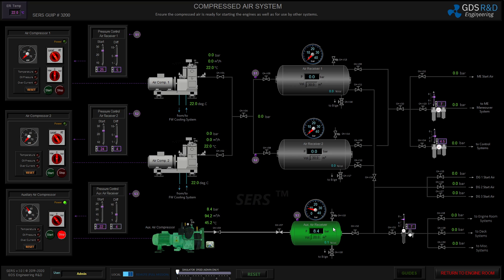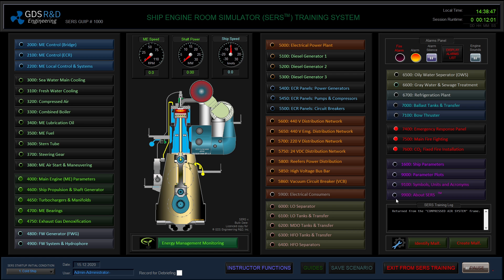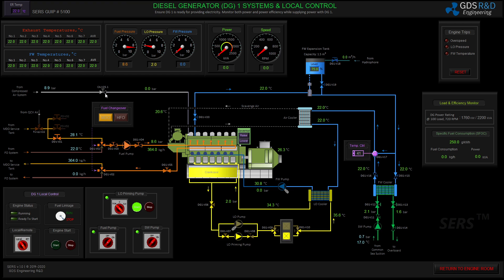I will go check my compressed air system — it is about eight bar of pressure here, and I will supply that air pressure to diesel generator number one. As soon as I engage the fuel linkage and switch it to the run position, my diesel generator should be ready to be started.